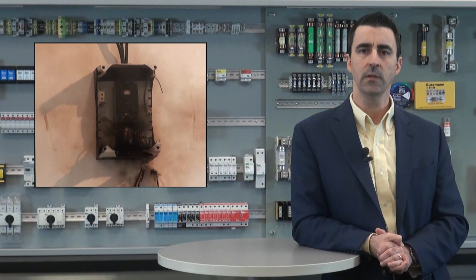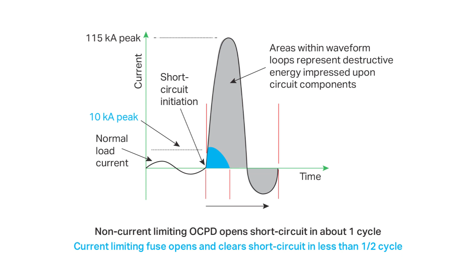Here is a diagram representing a worst-case single-phase waveform for the first few cycles. This condition is characterized as a bolted three-phase fault, where all phases are connected together. This results in the maximum thermal and mechanical stresses in the system. The short circuit current takes on an asymmetrical characteristic during these first few cycles until it becomes symmetrical. It is important to concentrate on what happens during the first half cycle after the initiation of the fault.